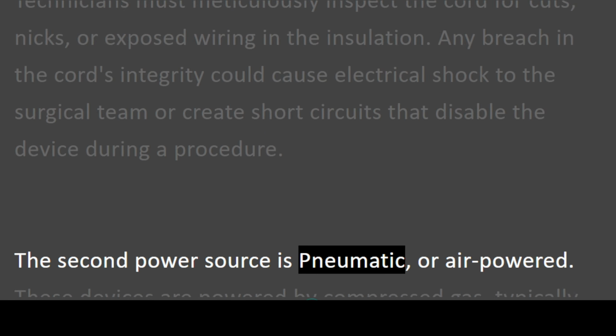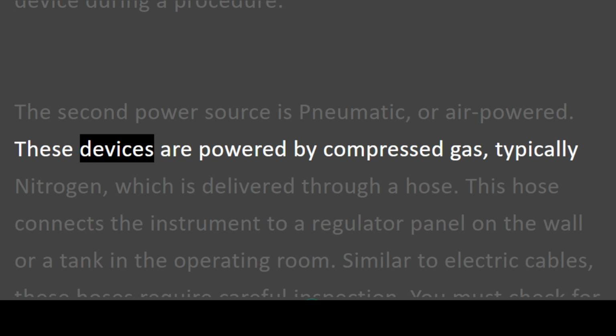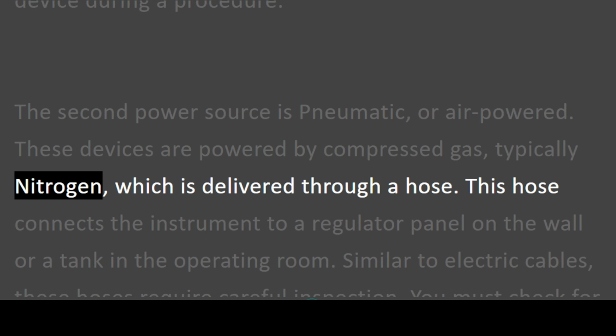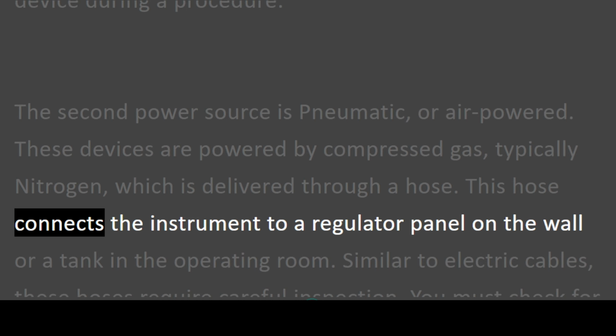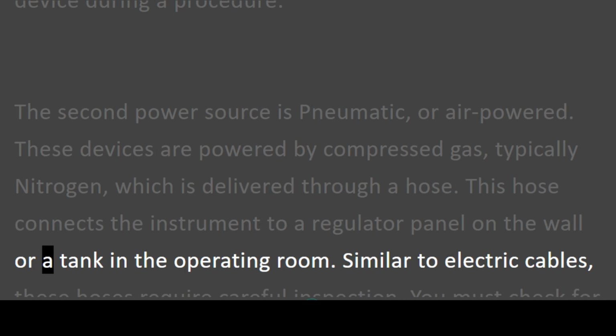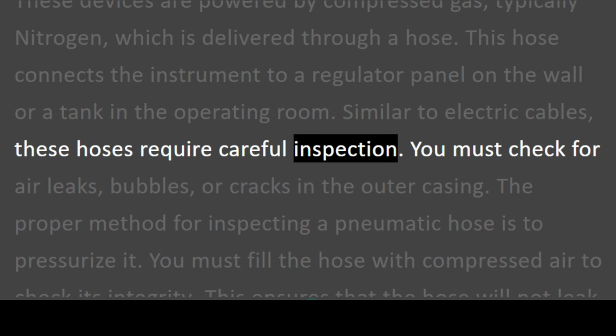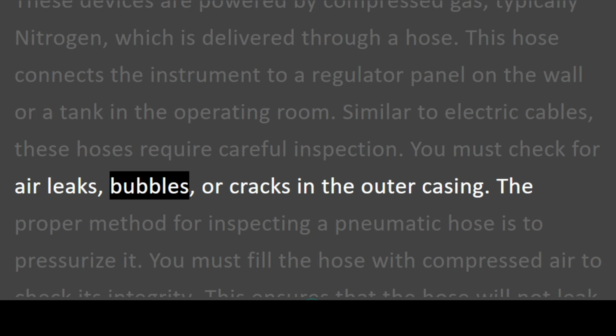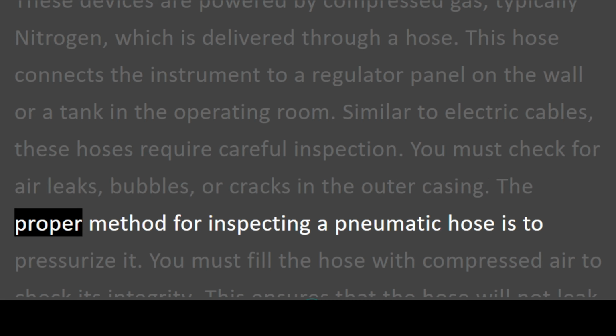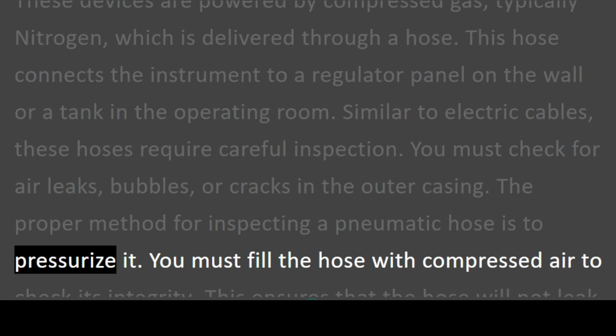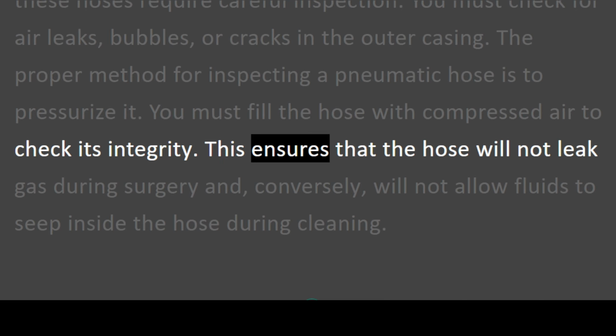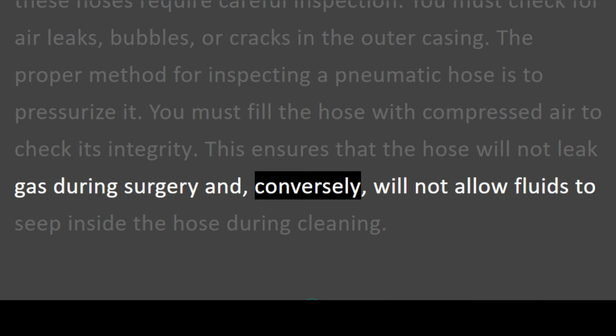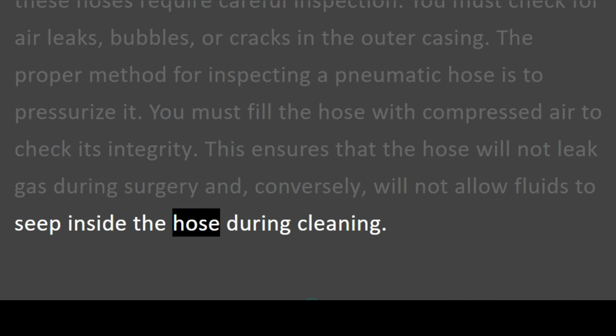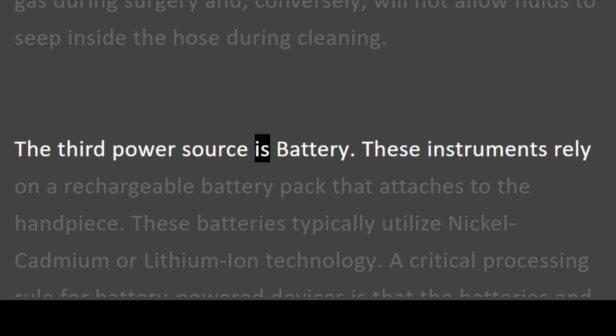The second power source is pneumatic, or air-powered. These devices are powered by compressed gas, typically nitrogen, which is delivered through a hose. This hose connects the instrument to a regulator panel on the wall or a tank in the operating room. Similar to electric cables, these hoses require careful inspection. You must check for air leaks, bubbles, or cracks in the outer casing. The proper method for inspecting a pneumatic hose is to pressurize it. You must fill the hose with compressed air to check its integrity. This ensures that the hose will not leak gas during surgery and, conversely, will not allow fluids to seep inside the hose during cleaning. The third power source is battery.